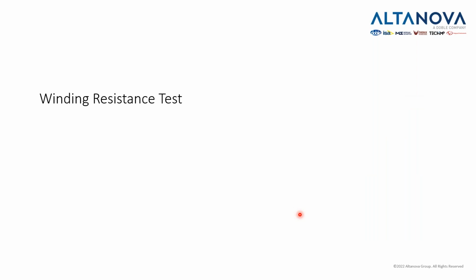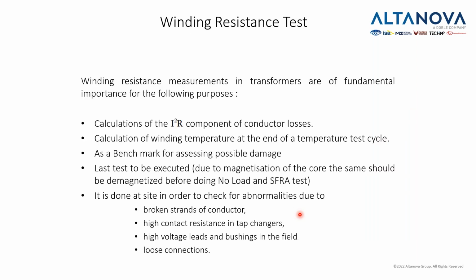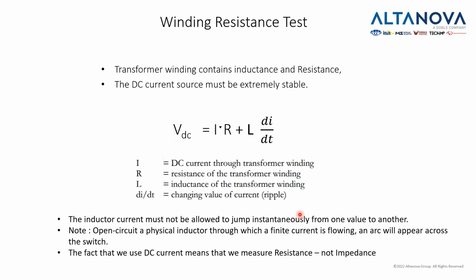Now the next test will be a winding resistance test. A winding resistance test is important because with this test, we can understand if we have some loose contacts inside. Usually, when we do maintenance, that's what we are looking for. There are some other reasons. What is also important to say is that this is usually the last test we do. And after this test is done, the demagnetization needs to be executed. And also don't do an SFRA test or a no load test after the winding resistance test, because the core will be magnetized, and because of that you may get different results.